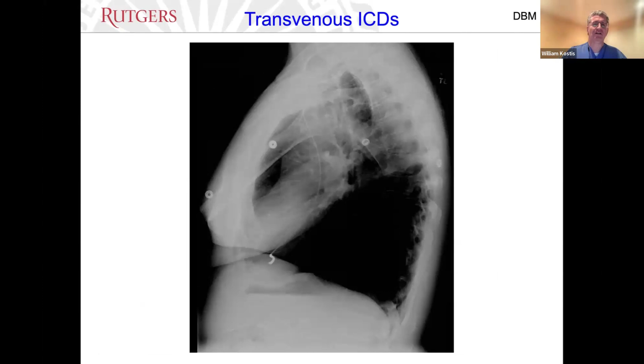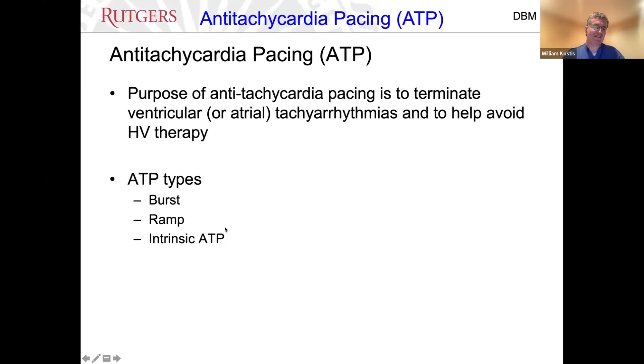So a little bit more about anti-tachycardia pacing. As we said, this is a technique designed to terminate ventricular, or in the case of atrial ATP, atrial tachyarrhythmias, but mainly it's to help avoid high voltage therapy when possible. You could do burst pacing, which is at a single cycle length, or ramp pacing, where you decrease the cycle length, in other words, pace faster. And there's a newer algorithm, something called intrinsic ATP, which I'll just touch on a little bit.